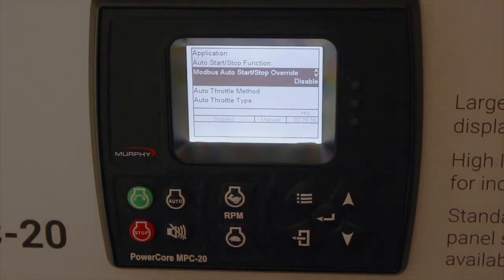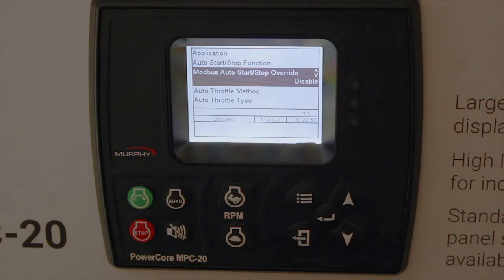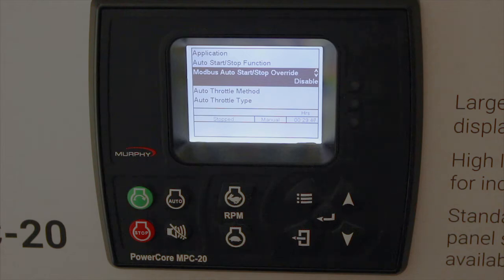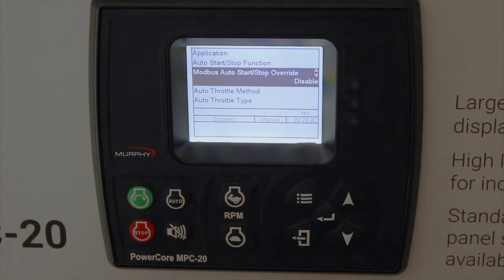Modbus auto start/stop override defaults to disabled. If you enable it, that allows a Modbus start independent of the start/stop types you have — a handy feature. For instance, if you had floats selected but wanted to do a Modbus start independent of that, you could do so by enabling this feature.